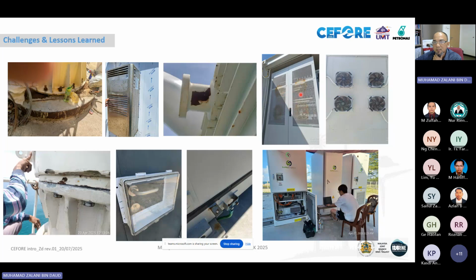As mentioned, the bus bar triggers alarms because of poor contact from the bus bar sensors. Because of this corrosion, the bus bar oxidizes and triggers an alarm, causing our BESS system to shut down.